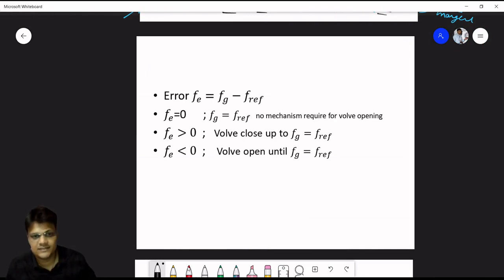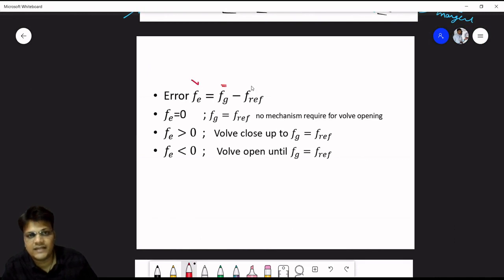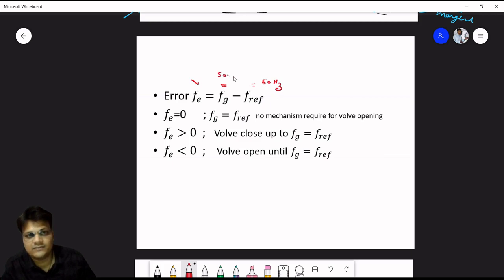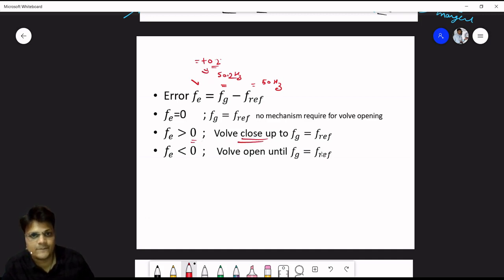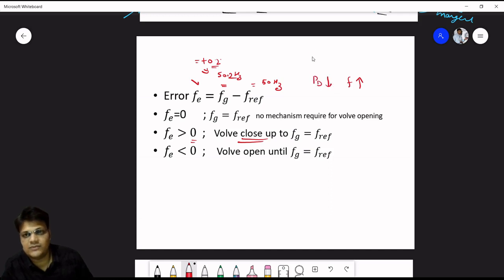Summary of the control logic: the error is Fg minus F_reference. The thumb rule is: when demand increases, frequency decreases; when demand decreases, frequency increases. If frequency increases to 50.2 Hz (error = +0.2), demand has decreased, so we close the valve and reduce steam flow to decrease generation. If frequency is less than reference (negative error), we open the valve to increase steam flow and generation.